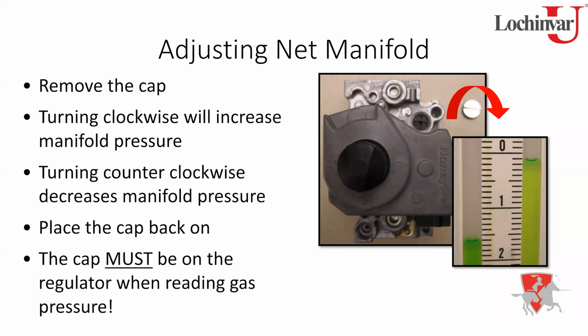There are certain mistakes that I've seen. People call me, hey John, I'm having some flame failure issues. We'll start going through the normal things. The first thing I'm going to check is whether it has been cleaned in the way we've already discussed in this presentation. Then we're going to see what our inlet gas is, and what it drops to when the valve opens, and all that. One thing that has happened in the past is people were messing around with the unit before they gave me a call, and they actually took that adjustment cap off, and that's why it wasn't lighting. Sometimes you forget about that cap. So make sure that cap is on there.